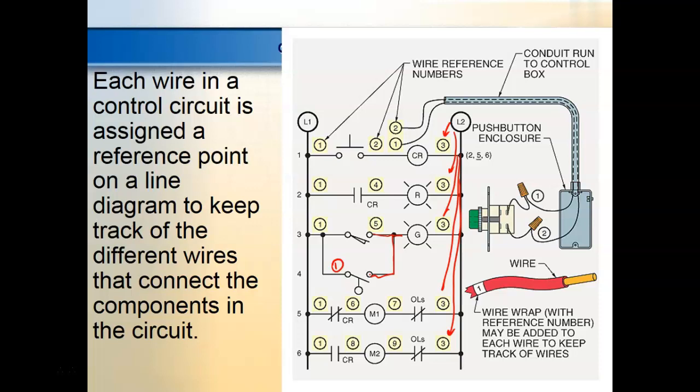Like I said, we were the original company of college that set these things up, and I can't tell you how old they were. But everything on there is still basically the same, except most new installations are not using 120 volts. Most new installations are using about 24 volts for their control circuit. And why? It's below 50 volts. And what's 50 volts?